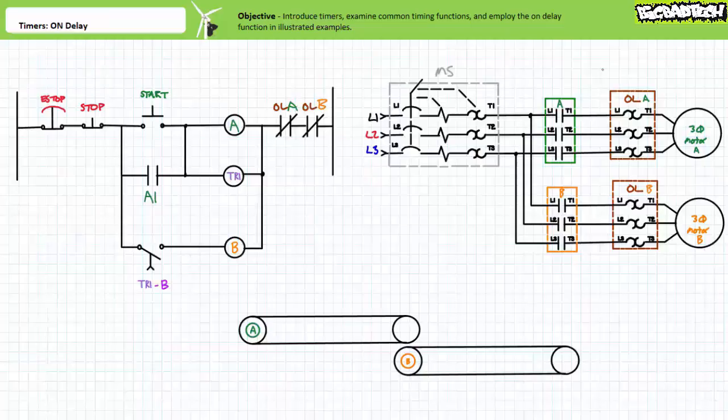The most basic application of on-delay timers is for scenarios in which one or more contacts must open or close a measurable time period after an input has been asserted. Recall that primary resistor, part winding, and Y-start delta run reduced voltage starters are all characterized by two distinct stages, start and run, and they necessitate a reconfiguration during the transition. Additionally, some types of solid-state soft starters, specifically those that are AC53B rated, must be bypassed during the run stage and given a chance to cool. All these applications are perfectly suited for on-delay timers, a timer function that delays the transition of associated contacts a predetermined period of time after the controlling input has been asserted. By all means, check this lecture out if you've got the time.